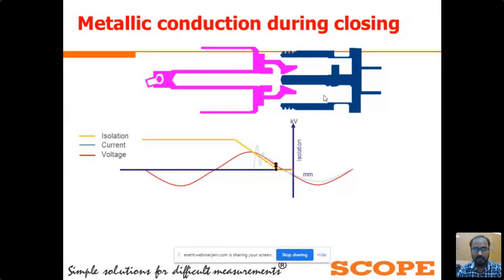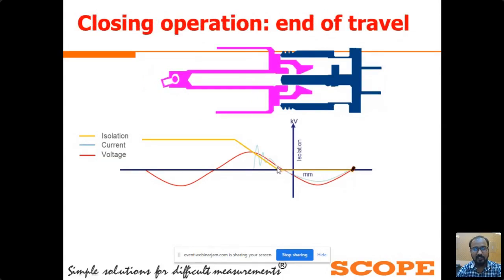Once the CB contacts are physically in touch with each other, after that we can see the sinusoidal current starts to flow. From this operation we have observed that whenever the dielectric strength between the CB contacts is less than the system voltage, the arcing current starts to flow between the CB contacts. During the closing operation of the circuit breaker, we call this phenomenon pre-arcing current between the CB contacts. During the opening of the CB contacts also, the arcing current will flow through the CB contacts whenever the dielectric strength between the CB contacts is less than the system voltage.